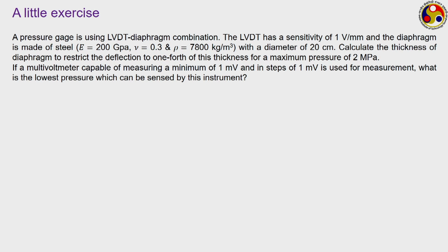Here we are talking about a pressure gauge which is using an LVDT diaphragm combination. That means it is an elastic pressure transducer, a diaphragm type, and there we are having an LVDT as the secondary transducer. That is, the pressure force gets converted to the deflection of this diaphragm, and then this deflection is sensed by this LVDT to give a voltage output.